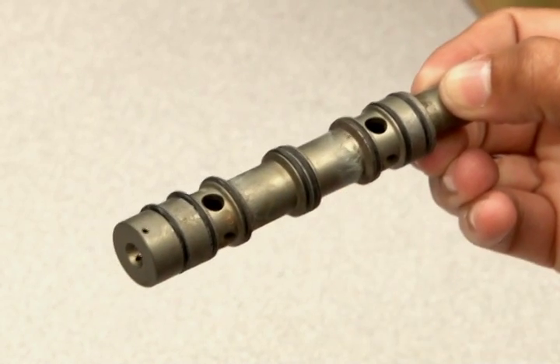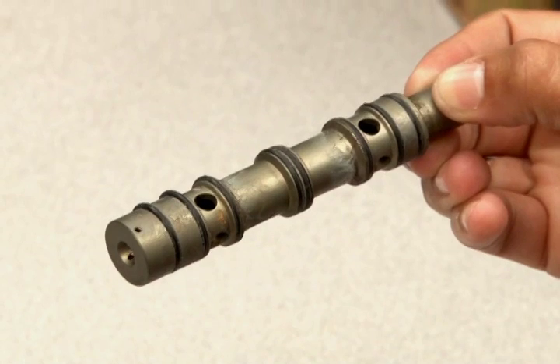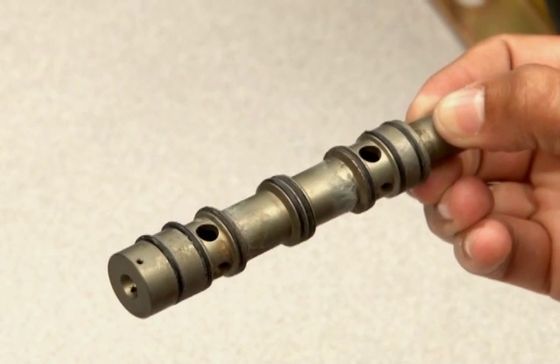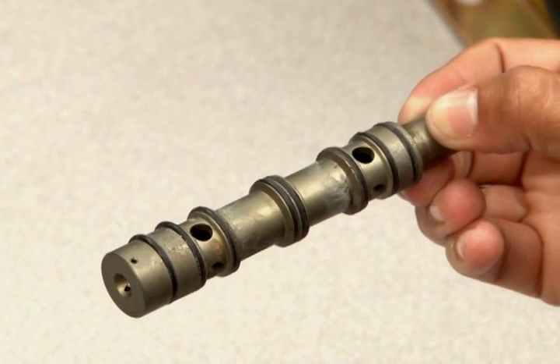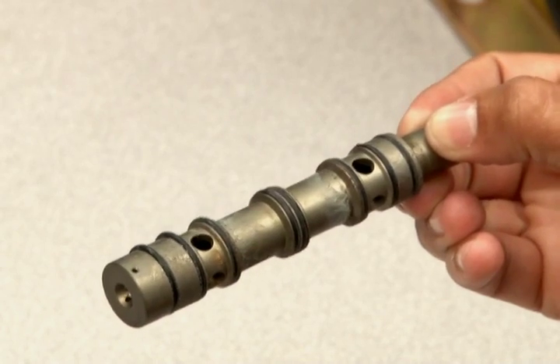Here is an example of worn O-rings. The O-rings lack roundness and appear flat. The spool is also dry and requires lubrication. Replacement of O-rings is recommended.